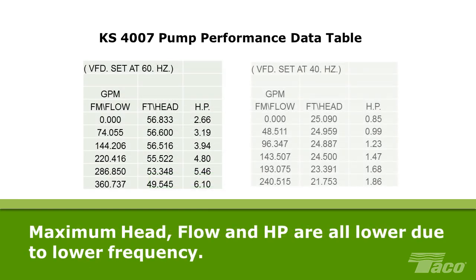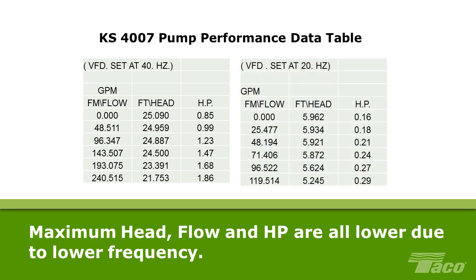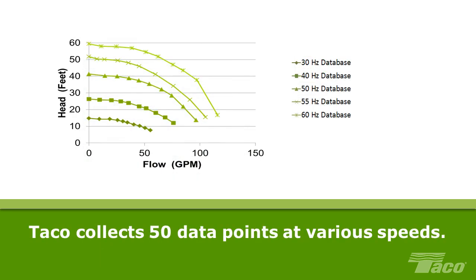Here's a data table for the same pump with a variable frequency drive set at 40 Hz. Note that maximum head, maximum flow, and maximum horsepower are all lower because the drive is delivering power to the motor at a lower frequency. Here's the same data with a variable frequency drive set to 20 Hz. The data shows the same pattern. Taco collects 50 data points at various speeds for each pump, and the computer interpolates the data for all the intervening points that make up the pump performance curve.